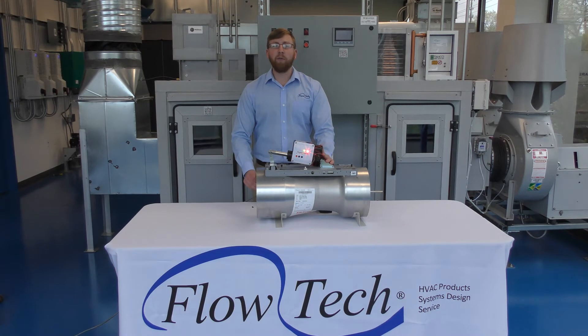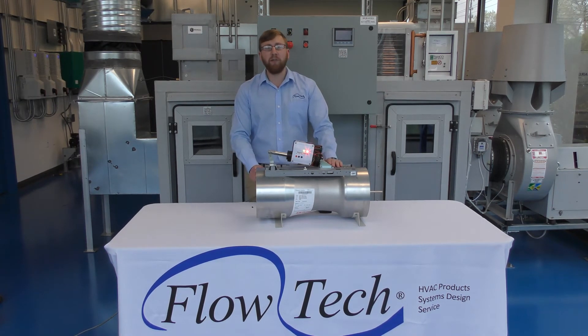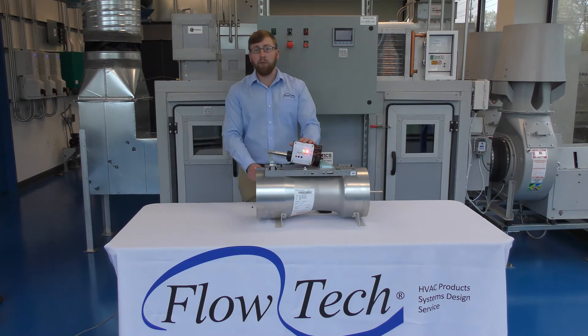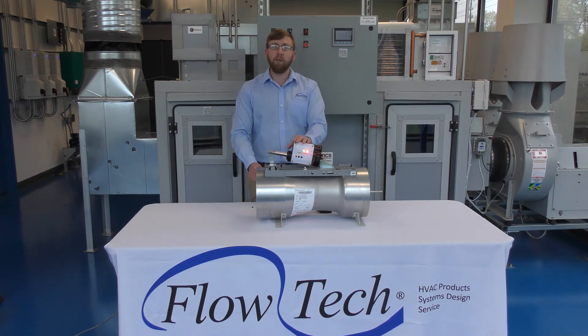Each valve controller and valve body is put on an NVLAP accredited air flow station at the Phoenix Controls factory. Each valve controller gets its own customized valve curve that gets downloaded into the controller, and what that means for you is the valve does its own PID loop and trimming.